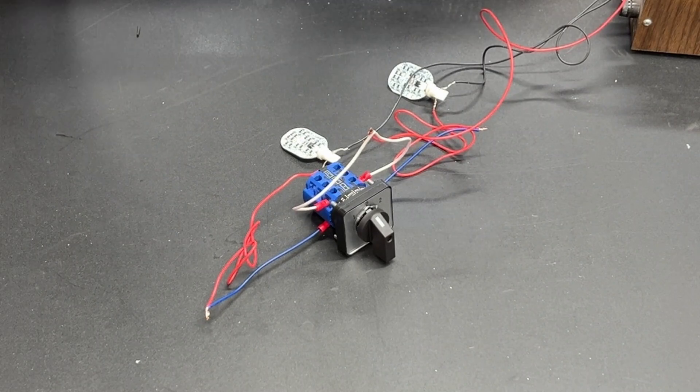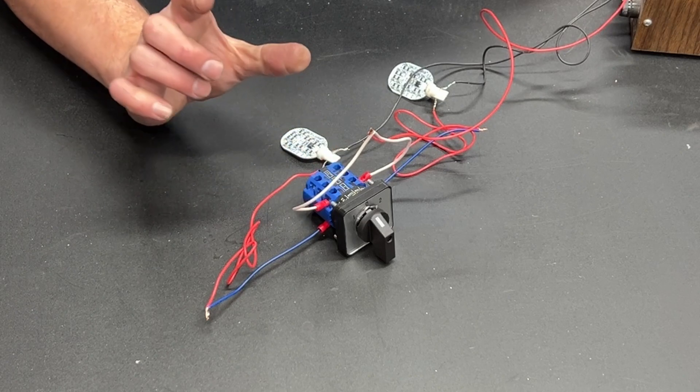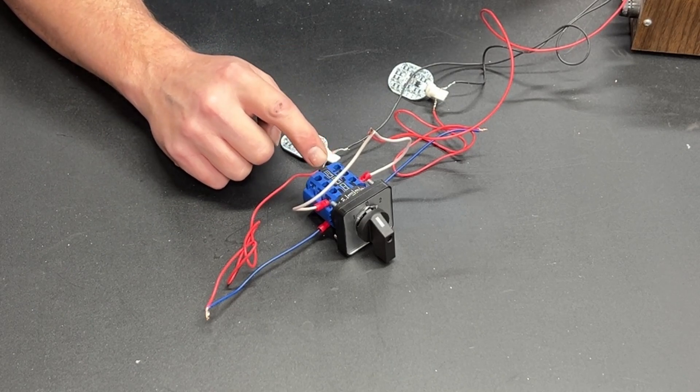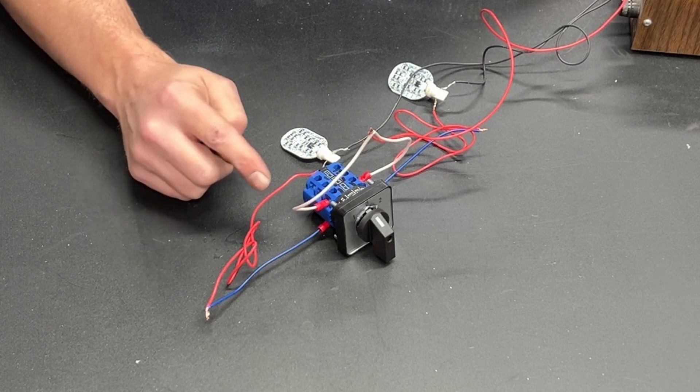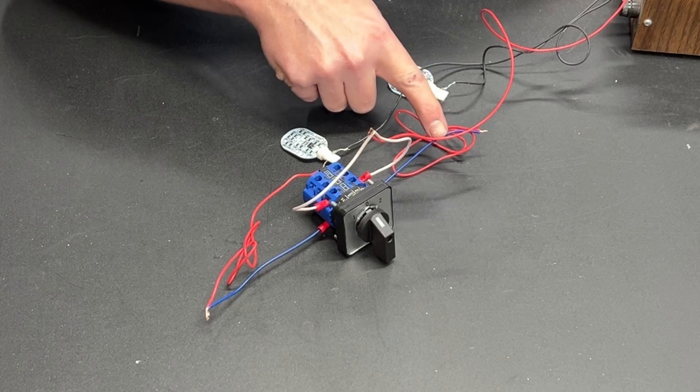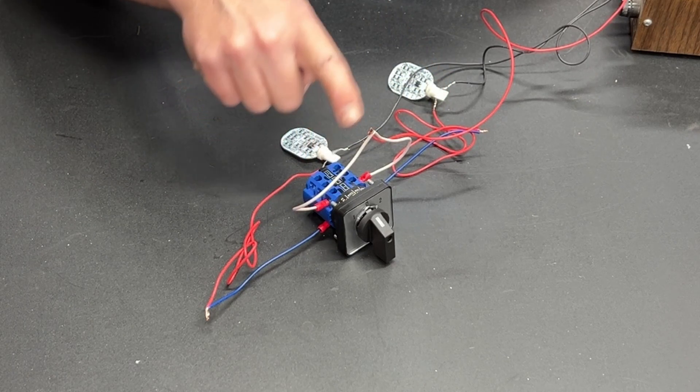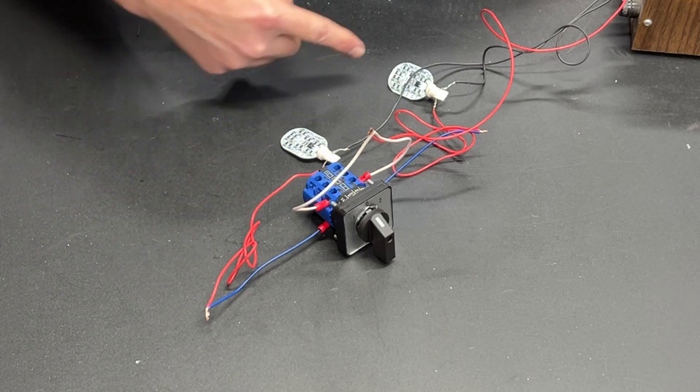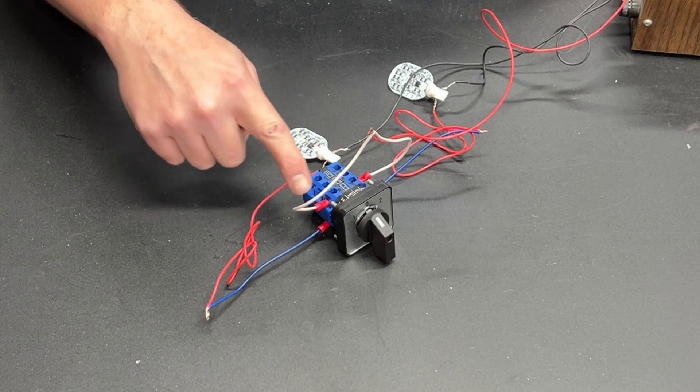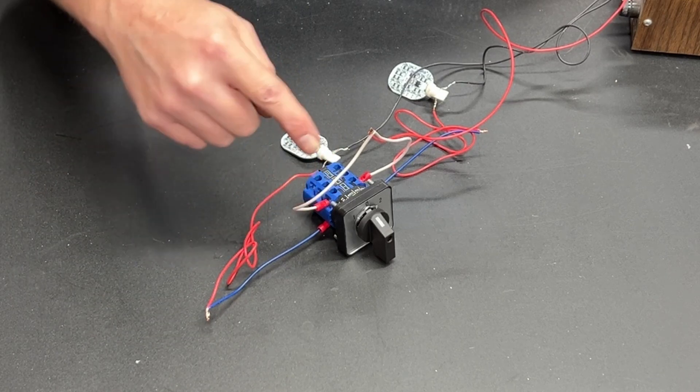All right so just like before we have power coming in on what is now our common. Now I want to be very clear here. This switch is not directional. In other words, had I taken this blue wire and attached it to this blue wire, that would have been our common and these two white wires could have gone to each of the light bulbs. So the switch doesn't care if power is flowing in here and out here or if power is flowing in on the blue and out on the white.